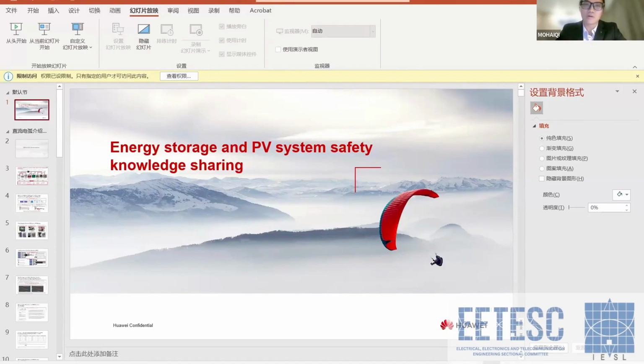Aaron Lee also mentioned that the DC side fault actually has different types. Like the string current backfeed due to string length difference: if within one MPPT, the strings have a big difference in the quantity of PV panels, the current will be different. Then there will be backfeed current that can damage the inverter or the optimizer, if you have one. Second is the risk of electric shock for the maintenance personnel, during maintenance or installation. And it is hard to extinguish a fire due to the high voltage of the module also.